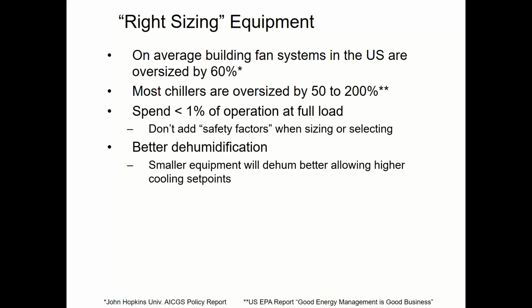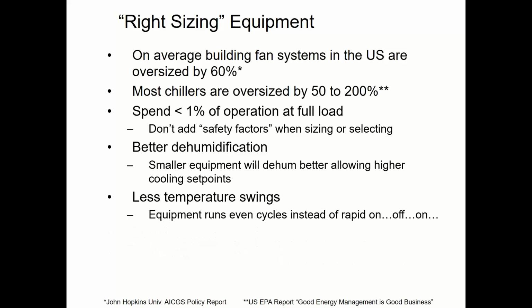I've sized it smaller, not too small, but smaller. And I have it a lot of stages so it can just continuously run without ever shutting off, and it's wonderful. And that's what we need to get to with all these other commercial systems as well. You'll have less temperature swings and comfort complaints if you can size the equipment smaller.